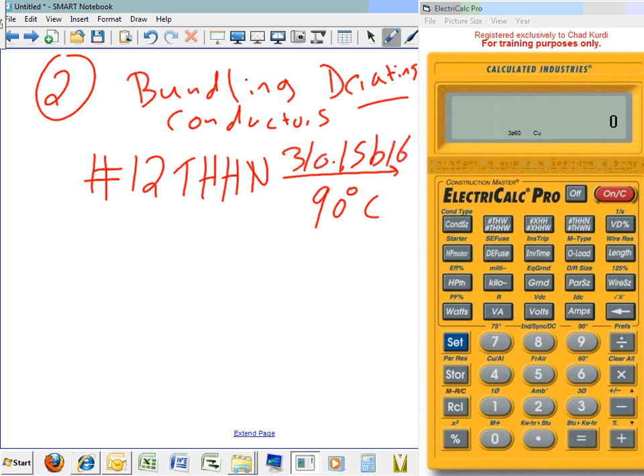Okay, so what do I get? If you guys go there, this will give you 30 amps. Am I right? Everybody got 30 amps, right? Under 90 degree. Okay, so that's 30 amps. Next, because of the 9, is it 9 or 16? Oh, by the way, since I have 16 conductors, and these 16 conductors are 3-phase and a neutral, and these neutrals are feeding lights, and lights have electronic ballasts in them, and electronic ballasts are harmonic offenders. They generate harmonics. So long story short, I have to count the neutral.